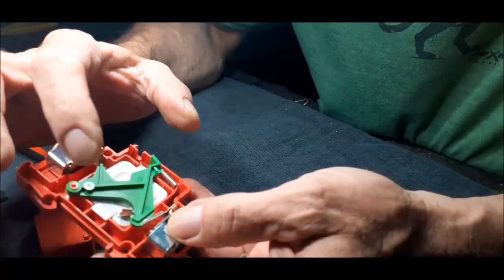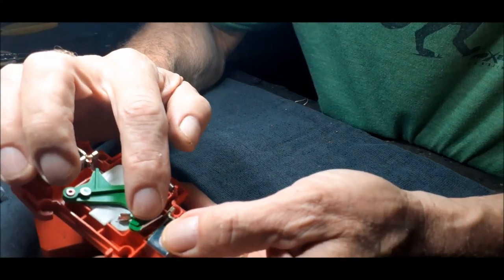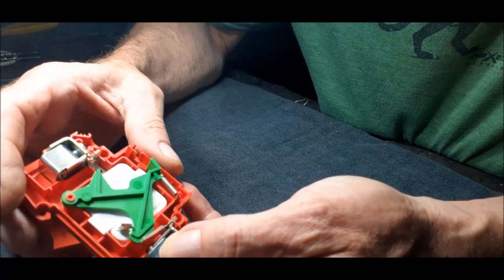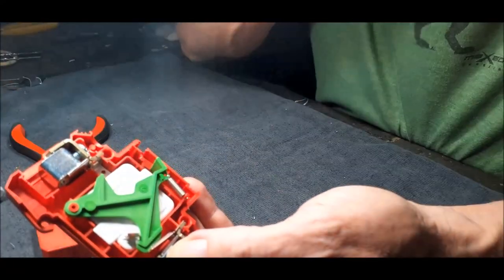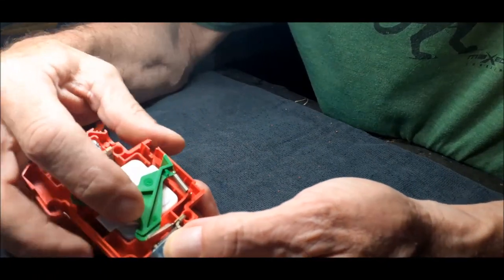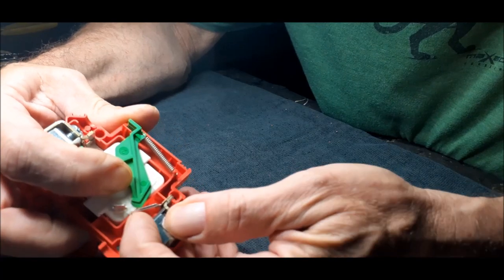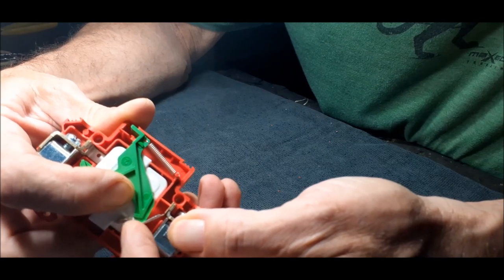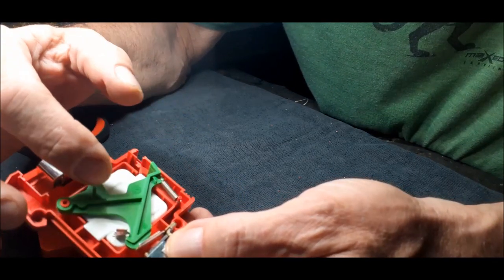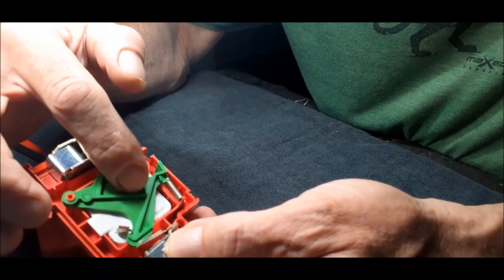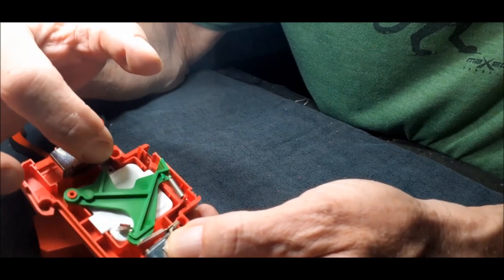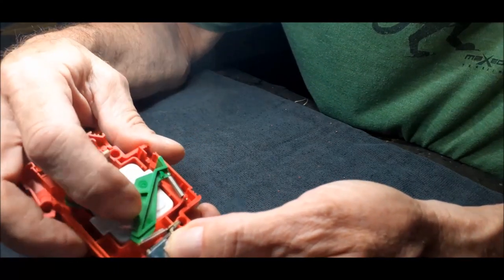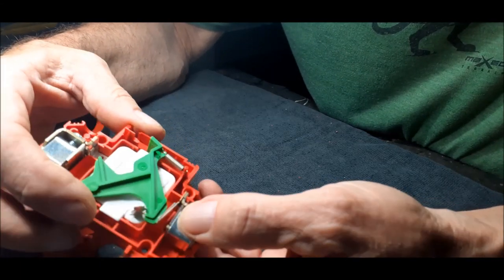But also, what happened now, there's no connection between the two points. So it will still work, but it won't help. It won't actually safeguard your line. As I said earlier, you can get maybe, I found that some of the units still show green. But it's shorted inside. Maybe the power surge wasn't big enough to melt the point there, but it still shorted out the MOV. And then it will trip your power anyway. So you get different situations as you go.